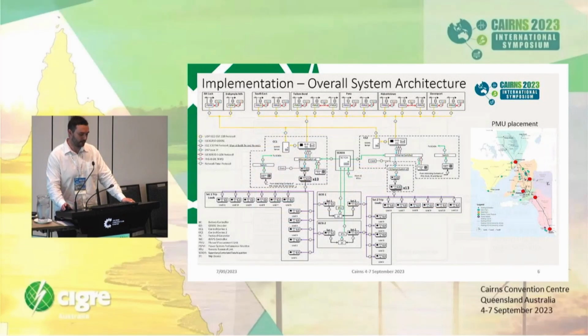So here's the slightly complex overall system architecture. You can see the PMU placement is spread across the state. There are 5 locations and 23 logical PMUs being streamed from these sites, and the scheme is redundant, so two controllers at 2 control centres. Those controllers have an onboard PDC that's forwarding the data internally to quite a powerful PLC engine that executes in hard real time, but it also forwards to a wide area monitoring system.